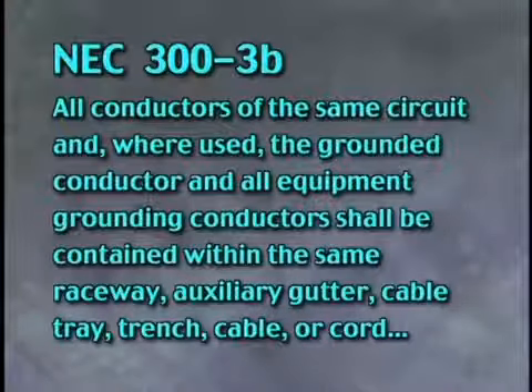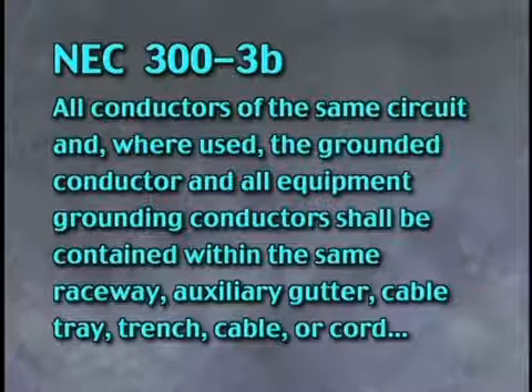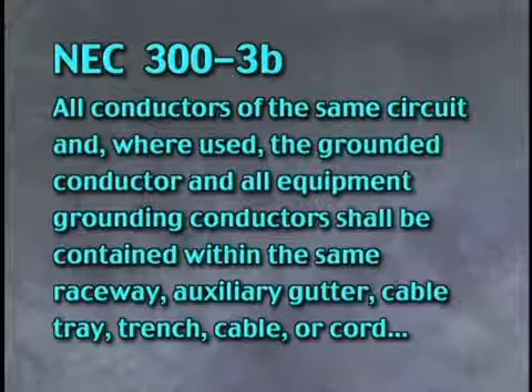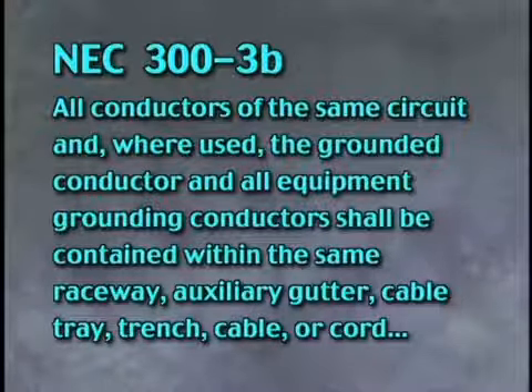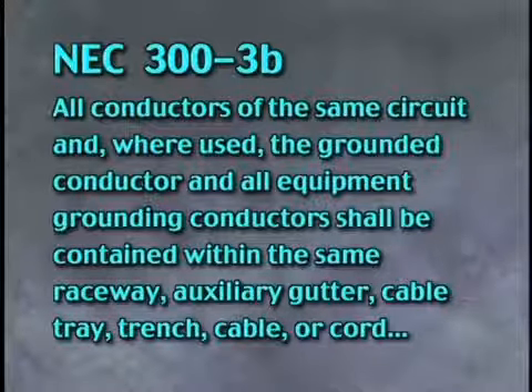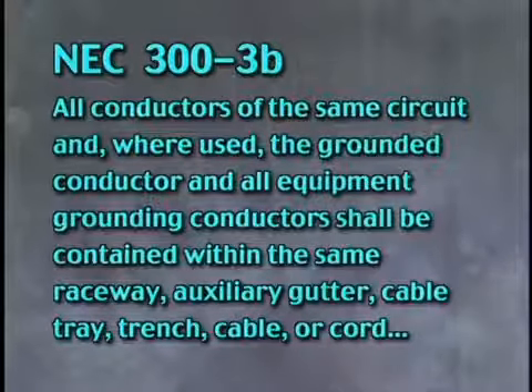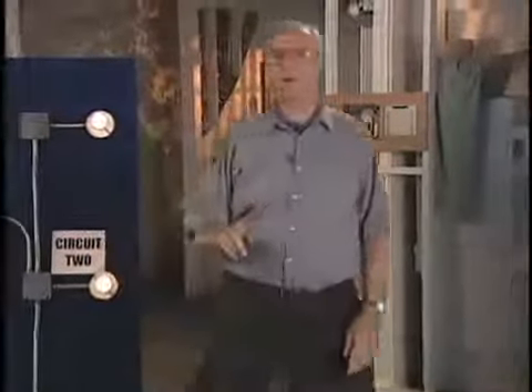Section 300-3B states that all conductors of the same circuit and, where used, the grounded conductor and all equipment grounding conductors shall be contained within the same raceway, auxiliary gutter, cable tray, trench, cable, or cord. Section 310-4 does not allow conductors to be paralleled, that is, joined at both ends, unless they are size 1/0 or larger. So you can't join two neutrals at a junction box when they're also joined at the panel bus.